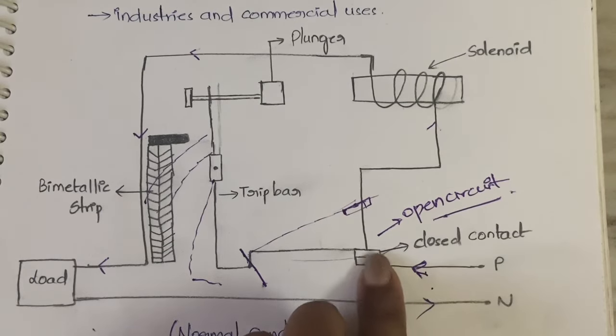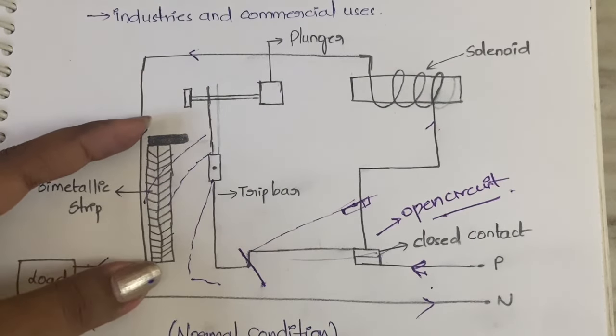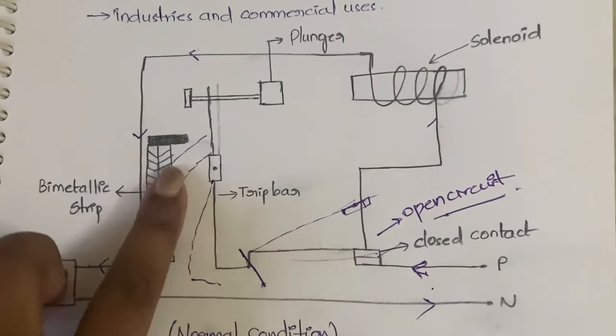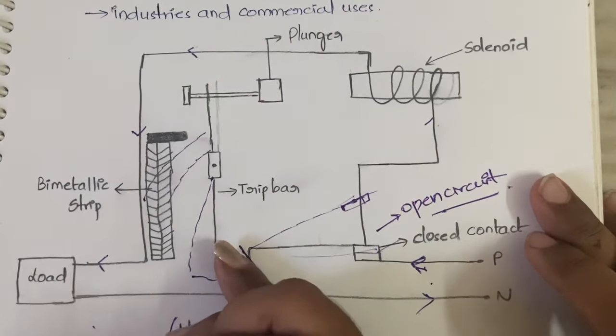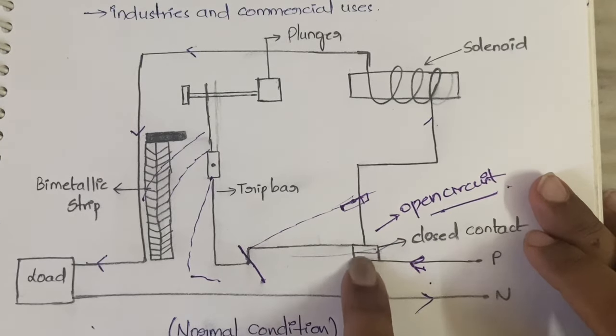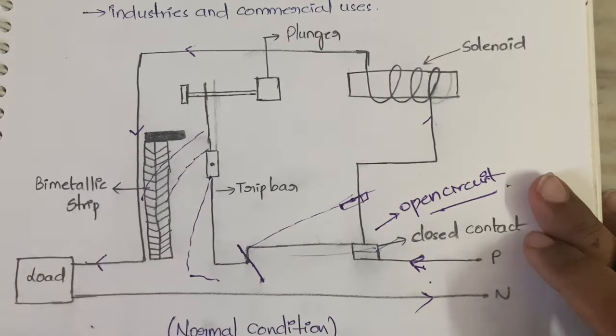To summarize the slow-increase case: excess current flows from the phase to the bimetallic strip, heat is produced, the strip heats up and bends, it hits the trip bar, the trip bar displaces, the closed contact is disturbed and raises up, becoming an open circuit, and ultimately no current flows.